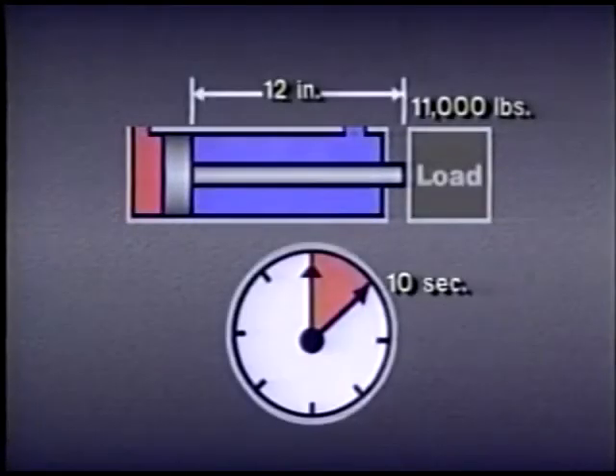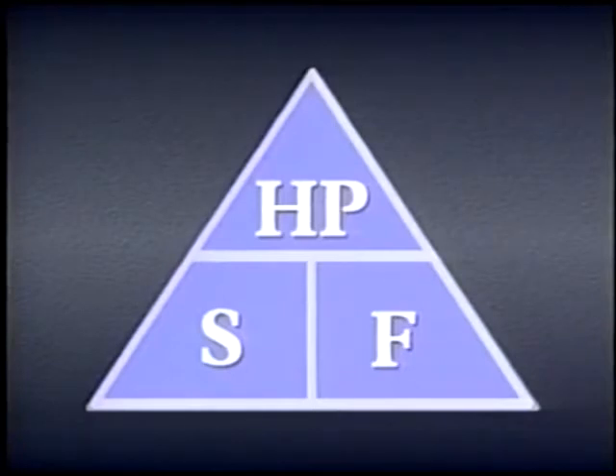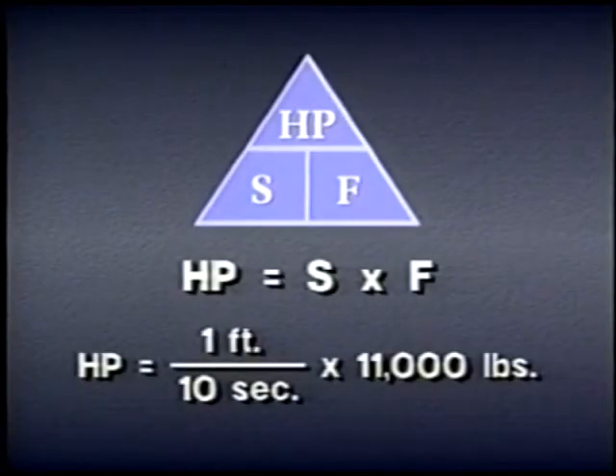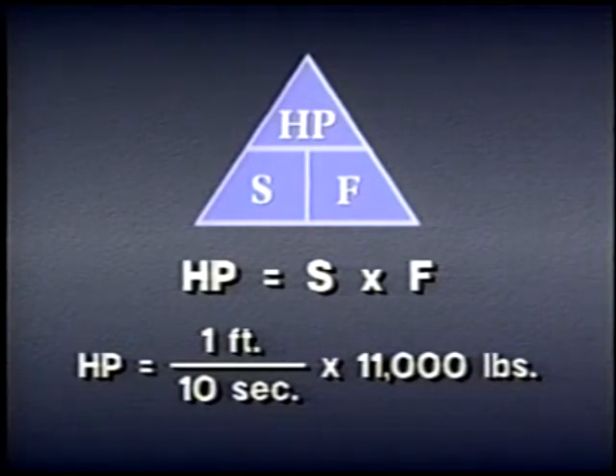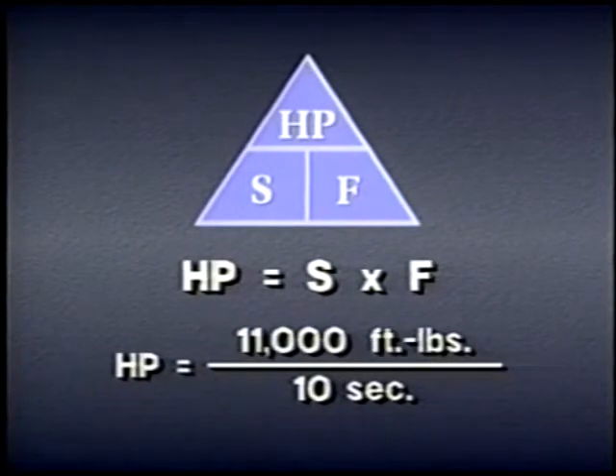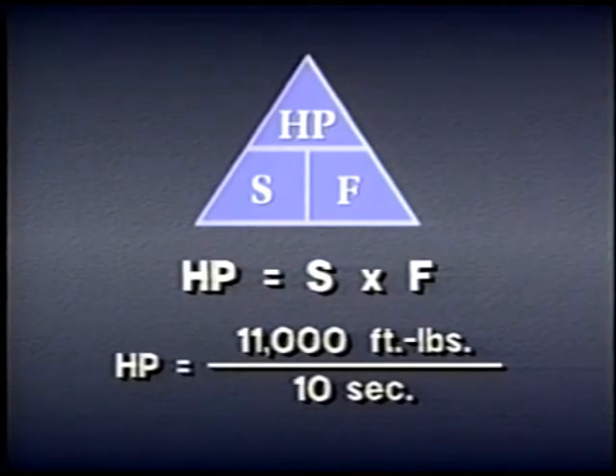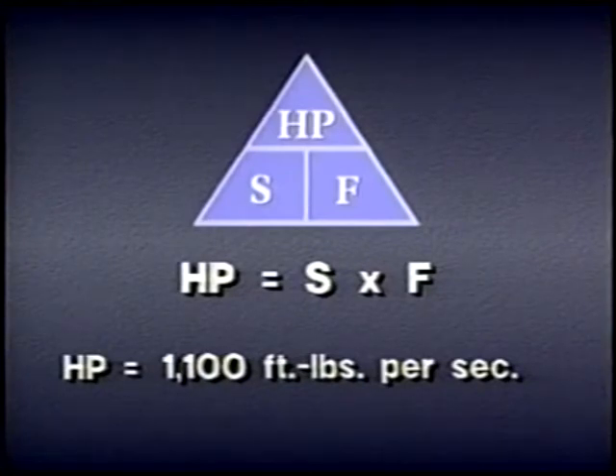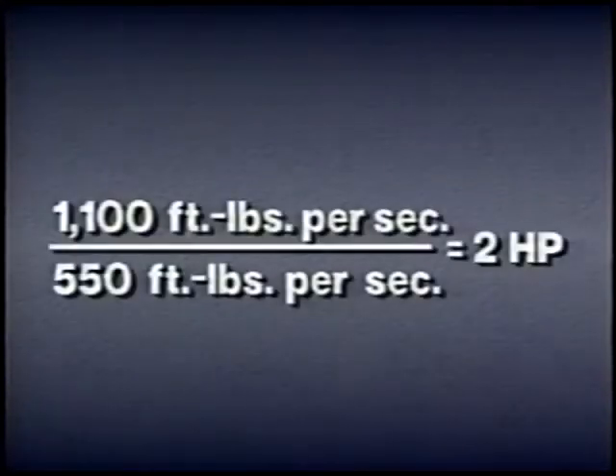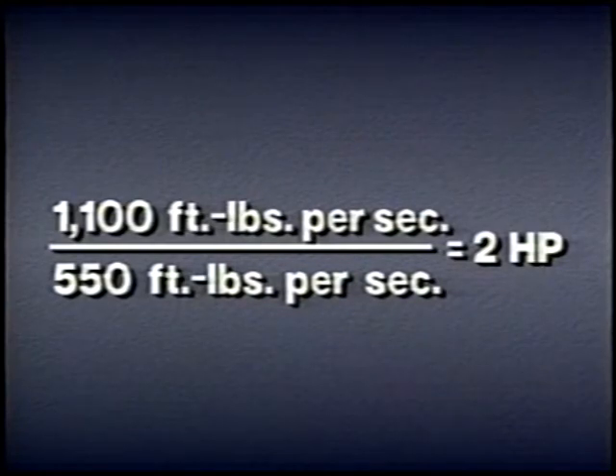For example, suppose we need to know how much horsepower it will take to move an 11,000-pound load 12 inches in 10 seconds. Horsepower equals speed times force. The speed is one foot every 10 seconds, and the force is 11,000 pounds. One foot times 11,000 pounds is 11,000 foot-pounds, divided by 10 seconds, giving 1,100 foot-pounds per second. Since one horsepower equals 550 foot-pounds per second, the cylinder must develop two horsepower.